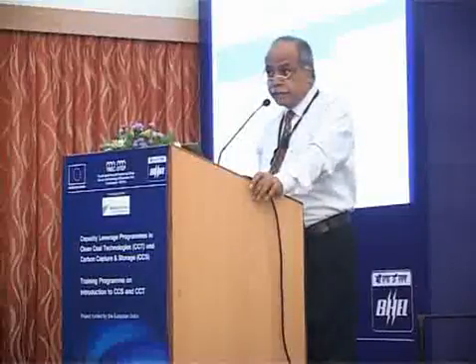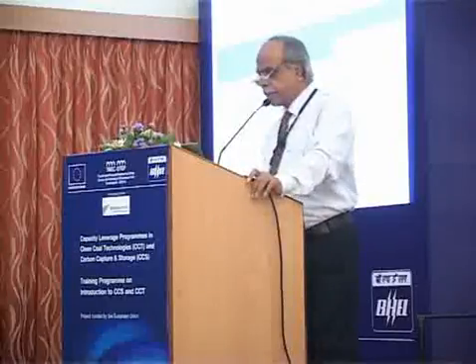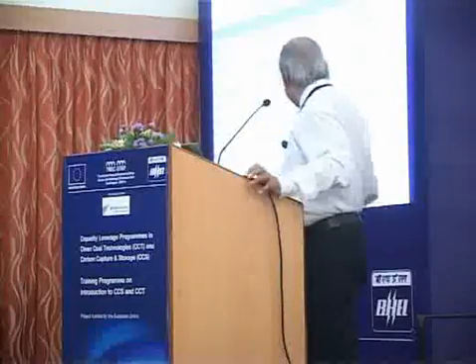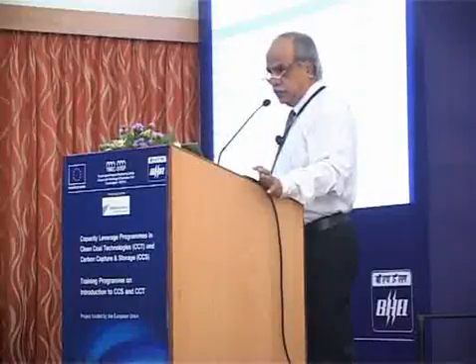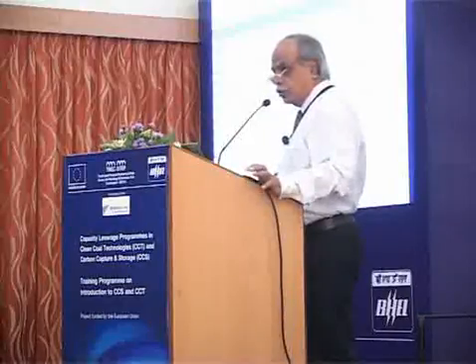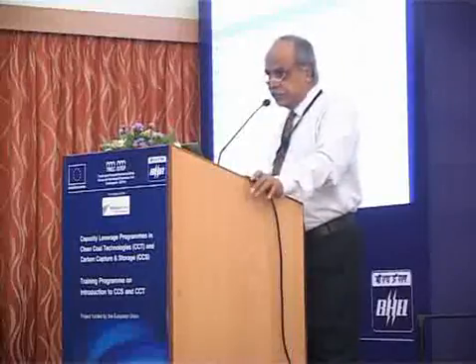Pardon? Oxygen and the NOx control factor. Okay, SOx we have considered. For the NOx, it was 59 ppm here. For this 59 ppm, no additional denitrification facilities were required. The 59 ppm is obtained after having a low NOx burner on the GT side. So once we have 59 ppm of NOx, which is acceptable to the process, no additional facilities are required for this purpose.